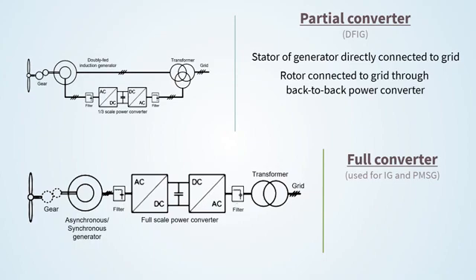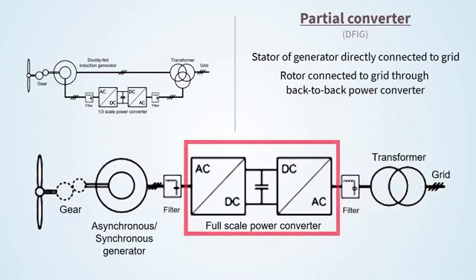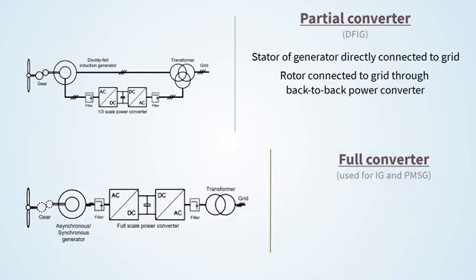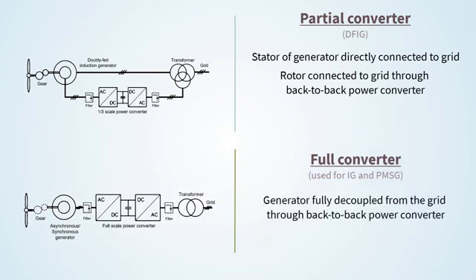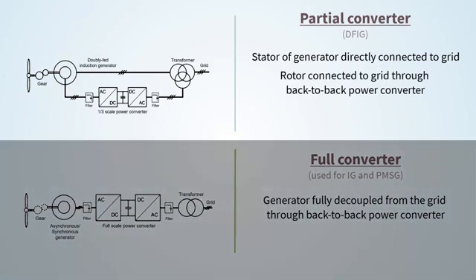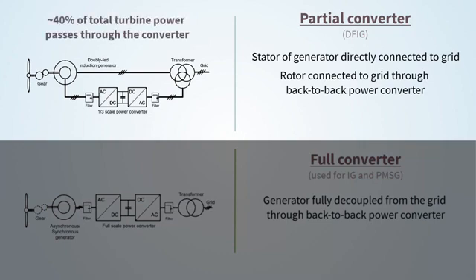And the full converter topology used for IG and PMSG permanent magnet synchronous generator, where the generator is fully decoupled from the grid through a back-to-back power converter. In the partial converter topology, only approximately 40% of the total turbine power passes through the converter, which allows a lower capital cost. This topology offers a power rating that goes from 1.5 to 6 megawatt.